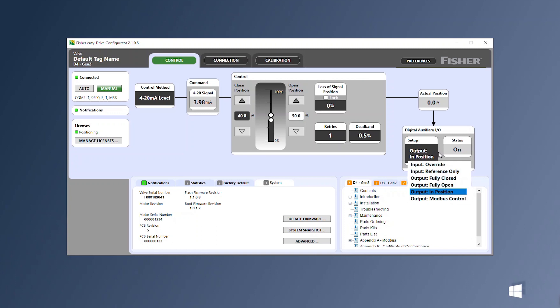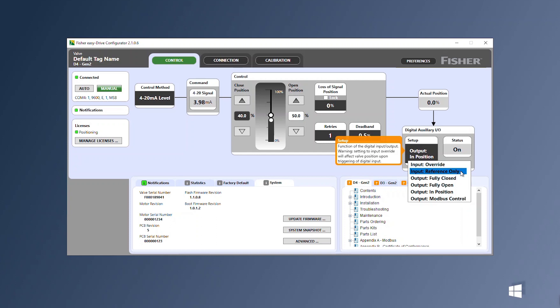If the I/O is set to input, closing a contact connected to the digital input terminals will result in the valve moving to that loss of signal position.